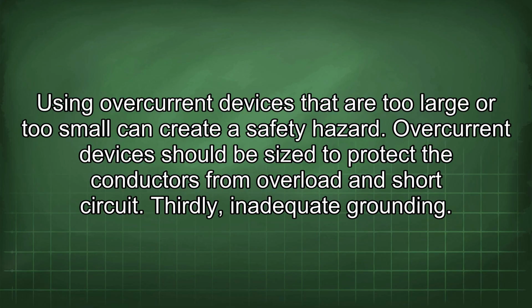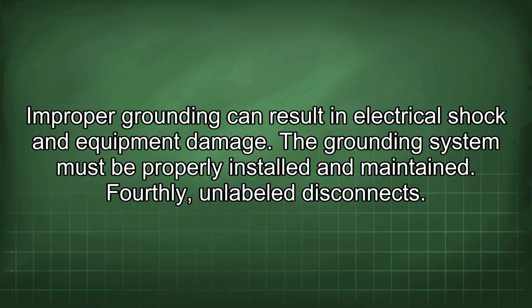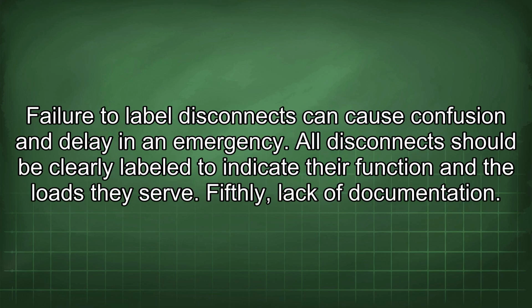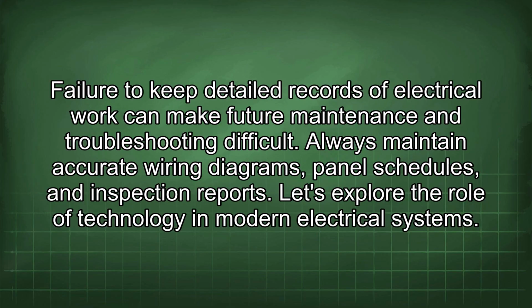Thirdly, inadequate grounding. Improper grounding can result in electrical shock and equipment damage. The grounding system must be properly installed and maintained. Fourthly, unlabeled disconnects. Failure to label disconnects can cause confusion and delay in an emergency. All disconnects should be clearly labeled to indicate their function and the loads they serve. Fifthly, lack of documentation. Failure to keep detailed records of electrical work can make future maintenance and troubleshooting difficult. Always maintain accurate wiring diagrams, panel schedules, and inspection reports.